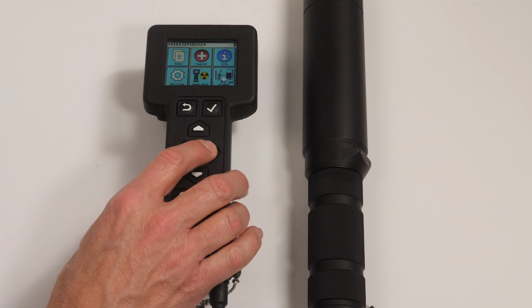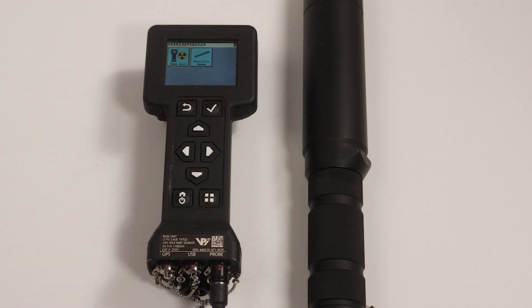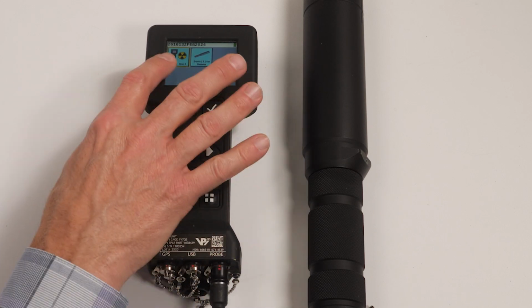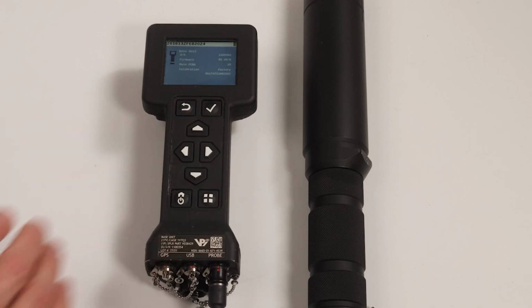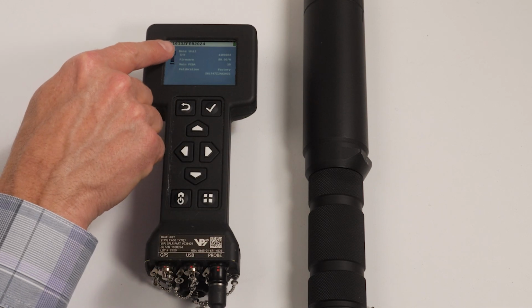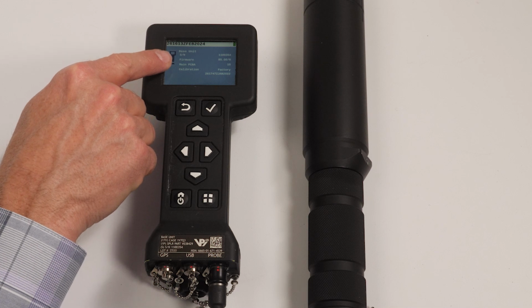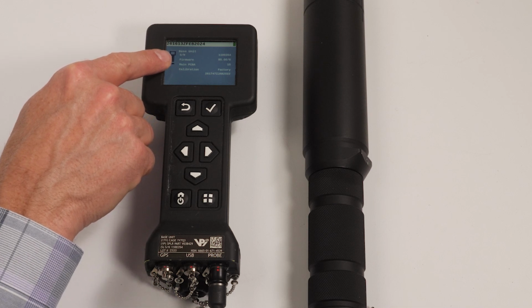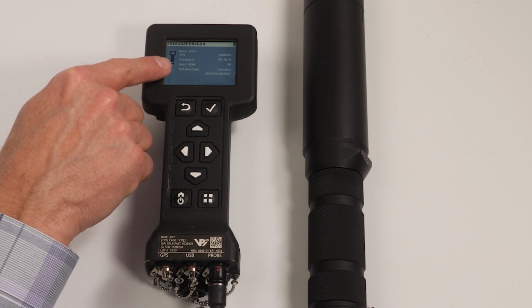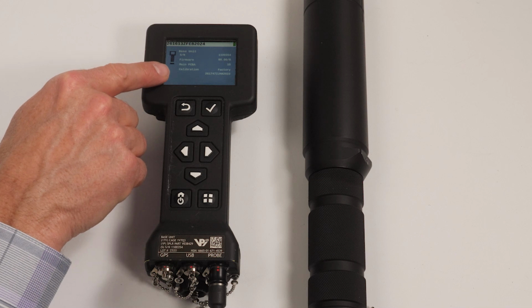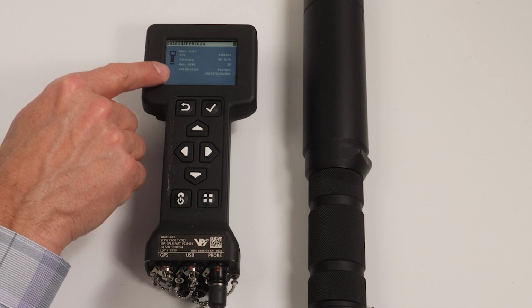The info screen displays system information about the base unit and attached probes. To access the info screen, press the menu key, highlight info, and press the enter key. Select either the base unit or an attached probe. You can access the following information on this screen: equipment serial numbers, the version of firmware running on the device, the hardware or printed circuit board version number, and calibration details.